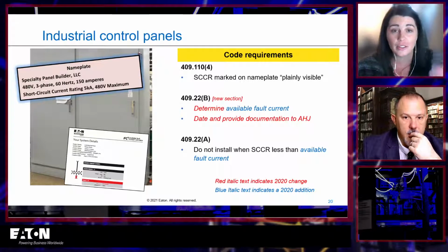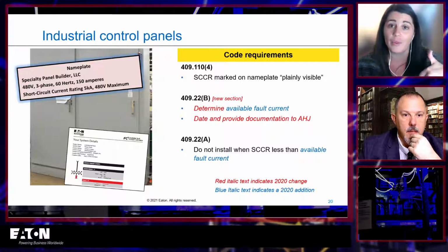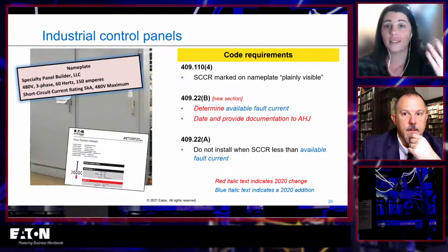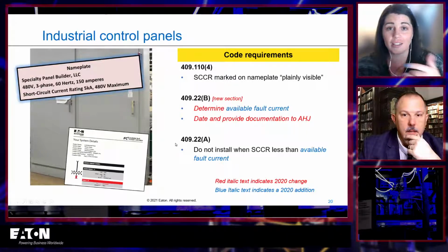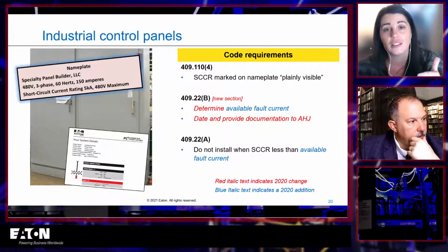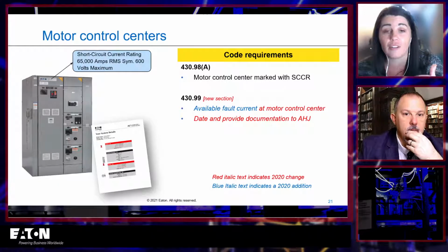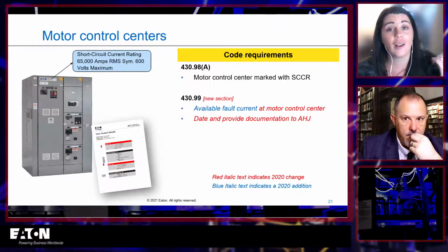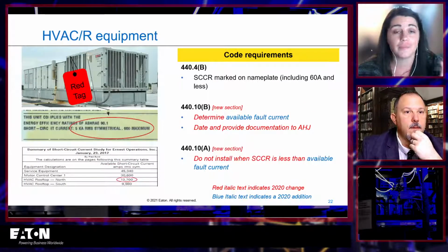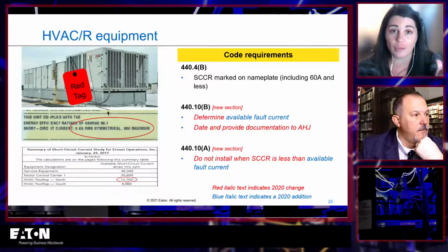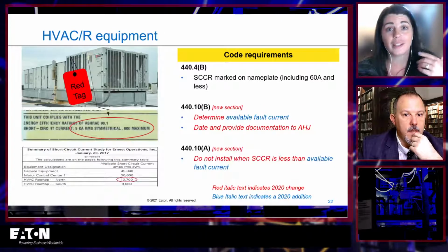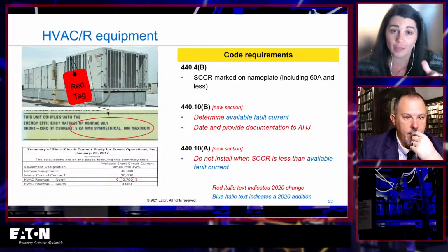So industrial control panels, don't install where the SCCR is less than the available fault current. Now you've got to know what it is. The same requirement. I mean, a lot of these are the same. I'm going to kind of fly through these because it's pretty repetitive. Motor control centers, same thing. Marked with the short circuit current rating, document the available fault current. HVAC equipment, same, determine that available fault current.